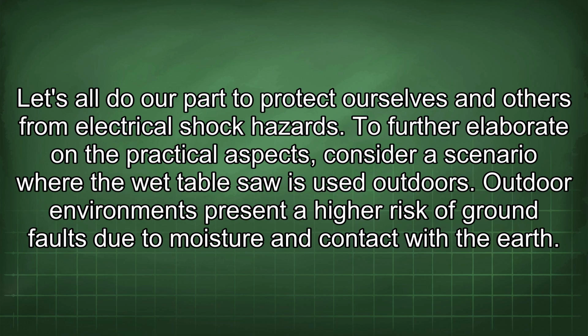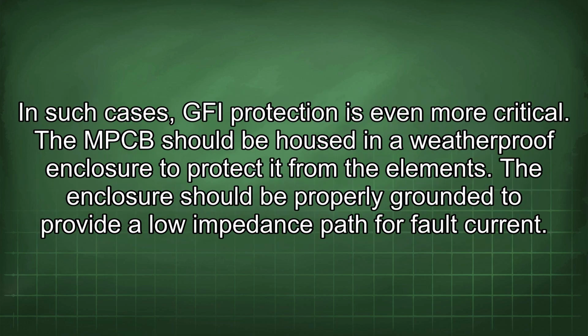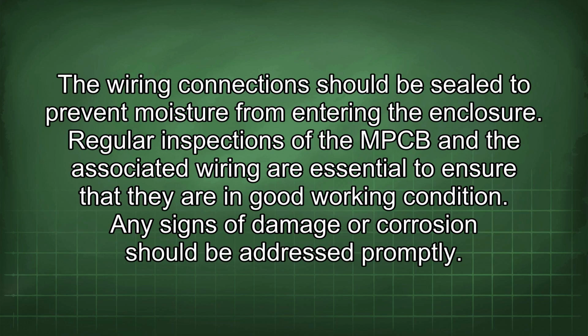To further elaborate on the practical aspects, consider a scenario where the wet table saw is used outdoors. Outdoor environments present a higher risk of ground faults due to moisture and contact with the earth. In such cases, GFI protection is even more critical. The MPCB should be housed in a weatherproof enclosure to protect it from the elements. The enclosure should be properly grounded to provide a low impedance path for fault current. The wiring connection should be sealed to prevent moisture from entering the enclosure.